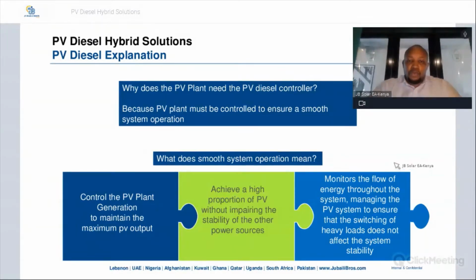And then you want to monitor the flow of energy. Is it coming from the PV side? Is it coming from the grid? Is it coming from the generator or the battery storage system? So you want to monitor the flow of energy throughout the entire system and make sure that when switching between the systems, this does not affect the stability of the system.